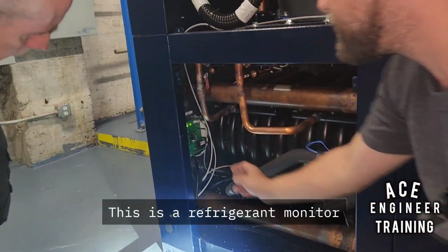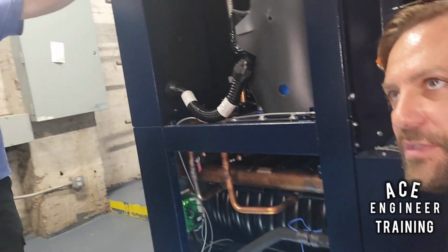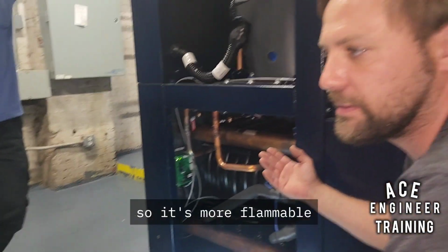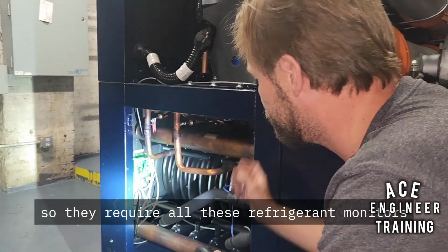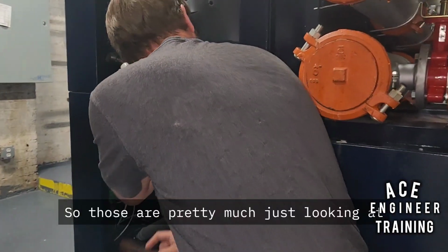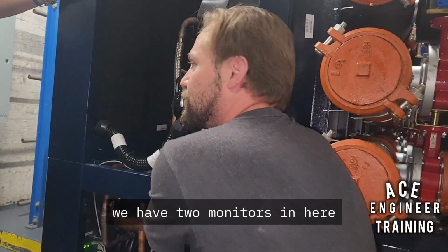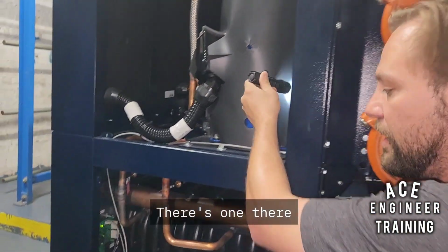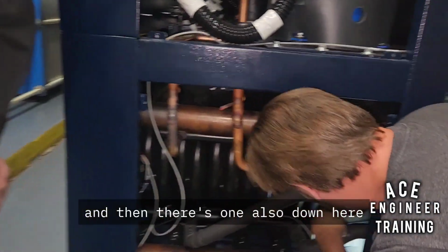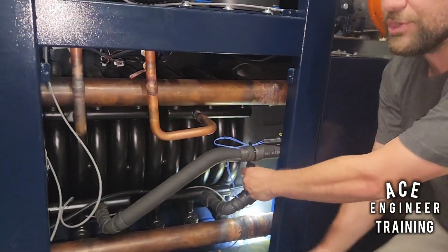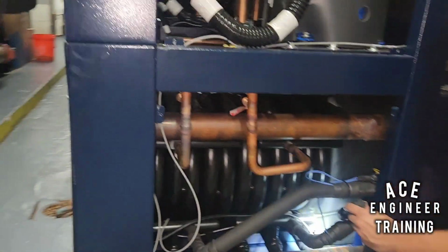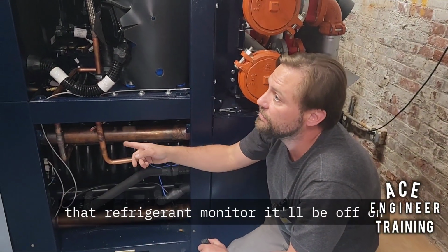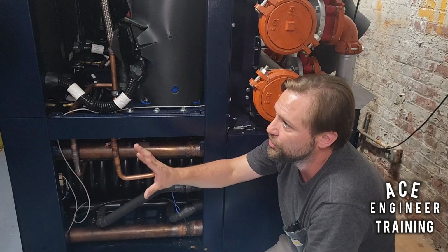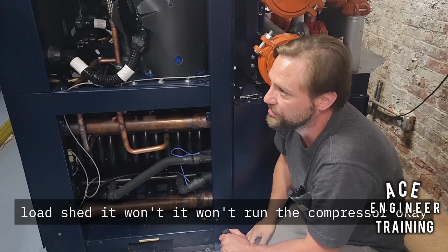Just to point out, you also have this board here. This is a refrigerant monitor. Okay. So this is 454B, so it's more flammable, so they require all these refrigerant monitors. Okay. So we have 2 monitors in here. There's one there, and then there's one also down here, which go to that device. Okay. And then if you ever see load shed on the screen, that's going to be that refrigerant monitor. It'll be off on load shed, so it won't run the compressor.